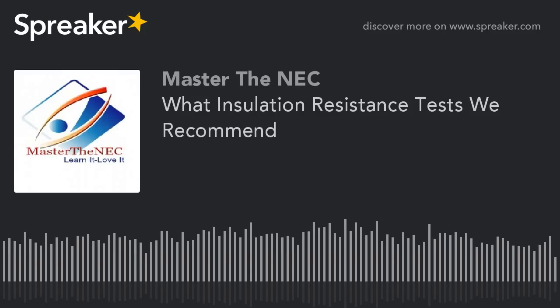Again, megohm meters are great for motor testing, testing the different windings for film breakdown, and the close proximity of very thin insulating material. It's good for that integrity testing. Usually you have an insulated component that's weak, and it separates from a grounded component, which allows for a return path, and that's how the meters really function adequately. So we discussed all that in the other radio show.